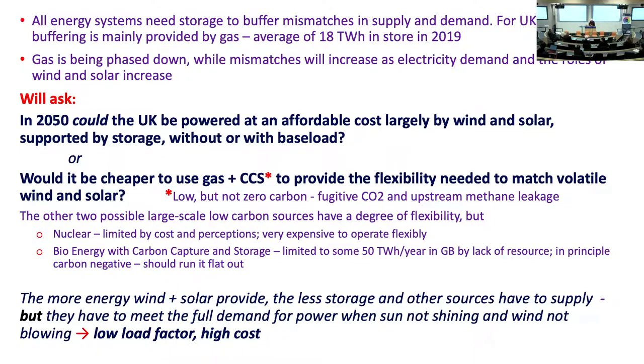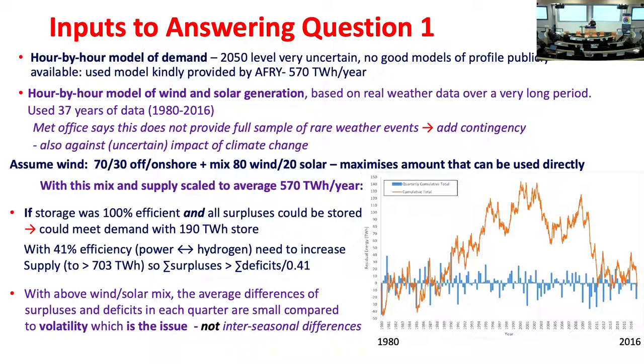To answer this question there are two things you need. First, you need to compare hour-by-hour supply and demand to ask when there's a surplus and when there's a deficit. We don't know what demand will be in 2050, and there are no decent publicly available hour-by-hour models, but luckily AFRY lent us their model — 570 terawatt hours, in the middle of the range of expectations for 2050. We've used the NINJA renewables data over 37 years. The Met Office said that's not enough to sample rare weather events, so we're going to put contingency into it.